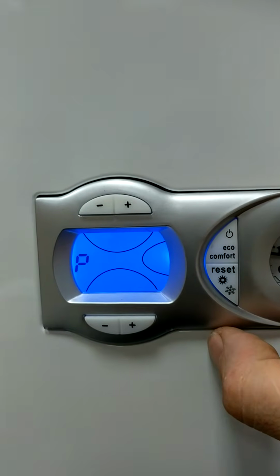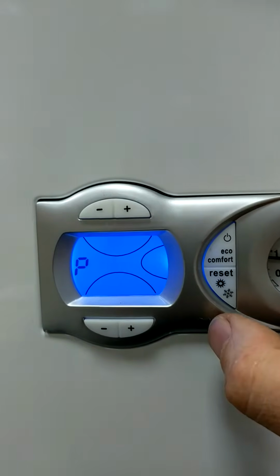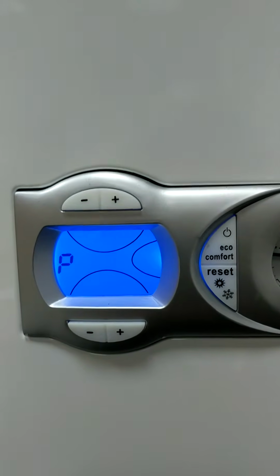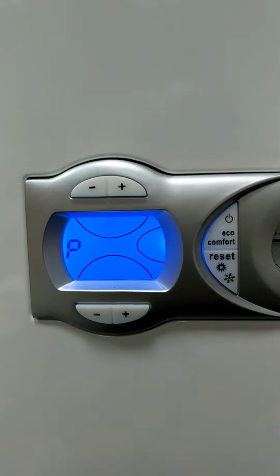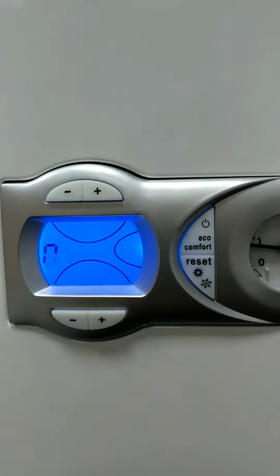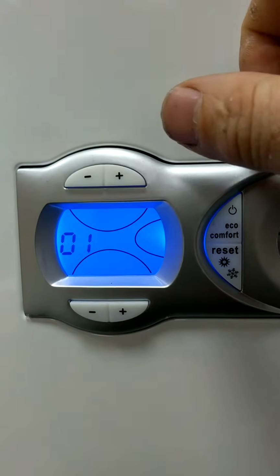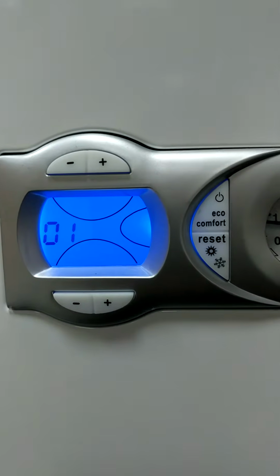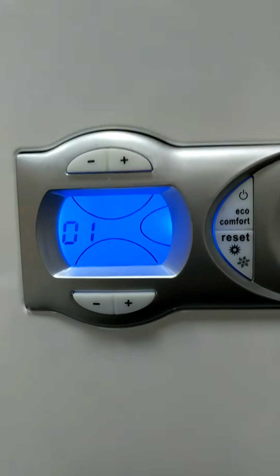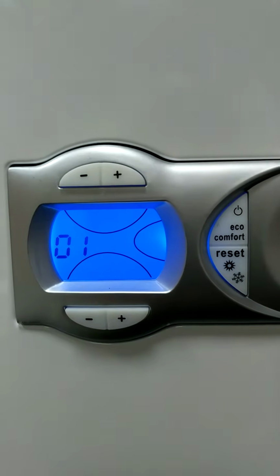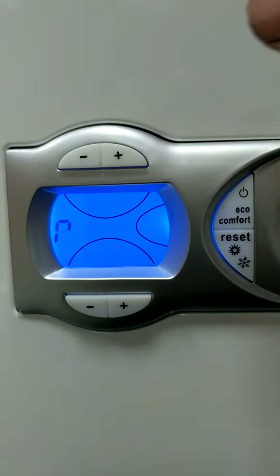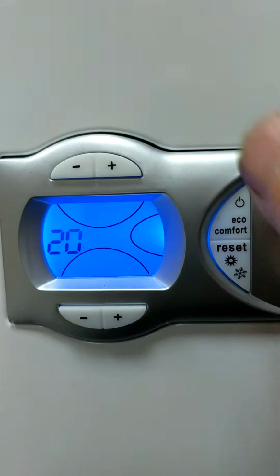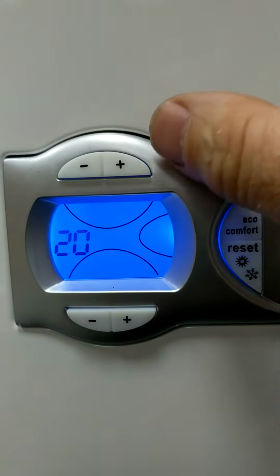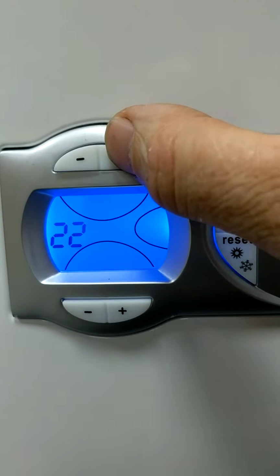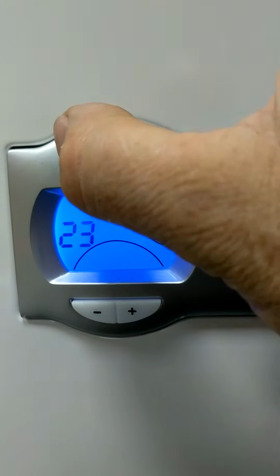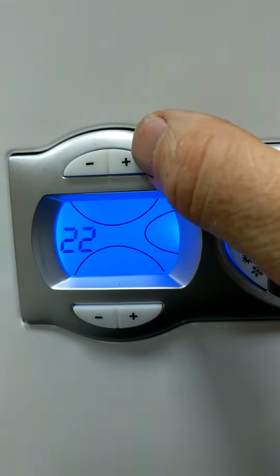First parameter we want to go to is the ignition pressure. This is how much ignition it takes to actually fire up the boiler. The burner is very small, so it doesn't take that much ignition. If you come across some of the boilers where they bang on ignition, maybe the ignition pressure is a little bit high. If it's not firing up and it comes up A1 fault, then it's probably too low. I normally recommend start around about 20 to 25, and you adjust that by plus or minus on the top, and you sort of go accordingly.